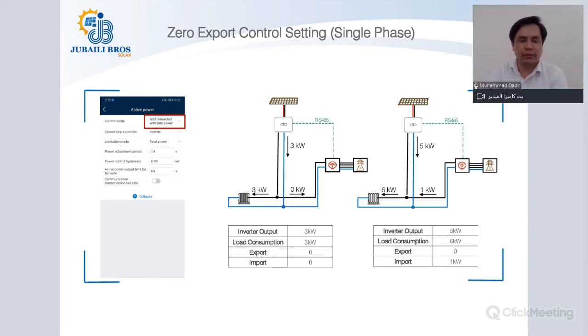Now talking of a single phase scenario, on how the zero export control setting would apply and how this would work. Let's suppose there is a PV system, as you can see on the right side in the SLD, that the solar PV plant is capable of generating 5 kilowatt while your load is 6 kilowatt. It means your solar PV system is generating less than what the load requires. So 1 kilowatt additional is taken from the grid side to accommodate the total power required by your load.